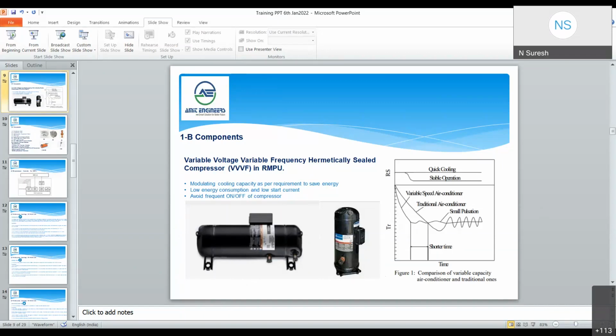Here the bold letter components are newly introduced in the Train 18 project, and were not in the previous projects or LHB. These components are not there. We have discussed condenser coil, evaporator coil, expansion valve, filter dryer, sight glass. These are all common components in the system. Whereas this is the discharge line check valve. Whenever the compressor gets switched off, there should not be any liquid fed back. This is mechanically designed, so whenever the system switches off, it will not allow any refrigerant to reverse inside the discharge line. This is basically the protection of the system.